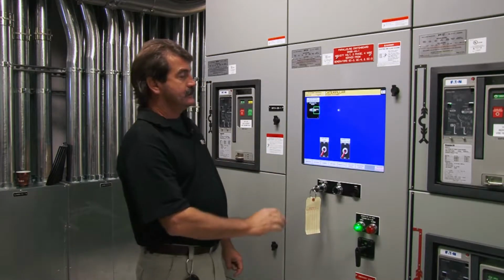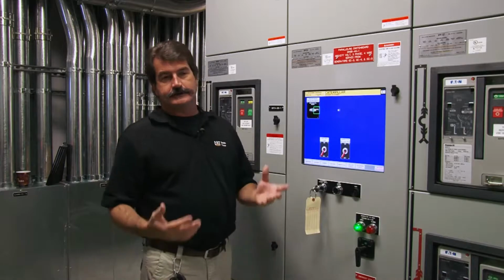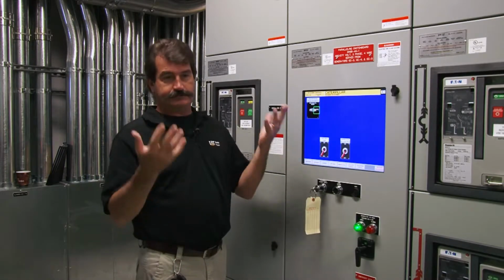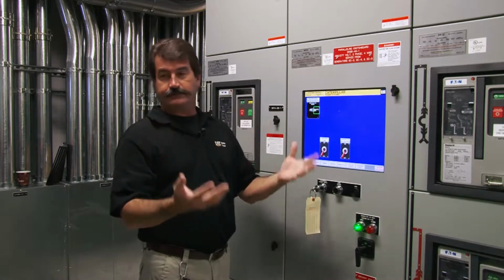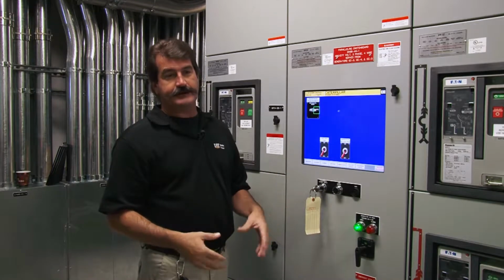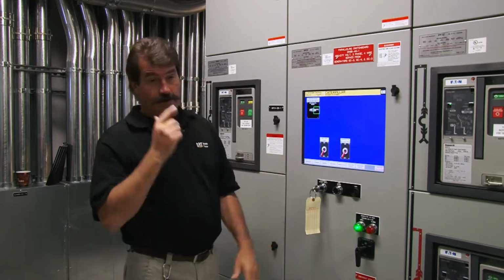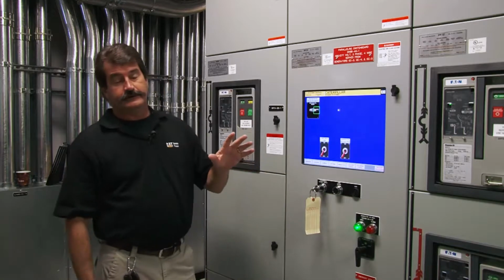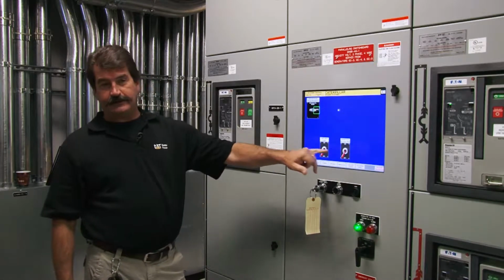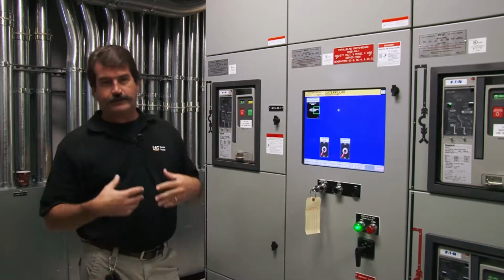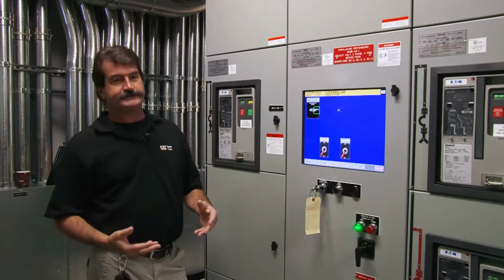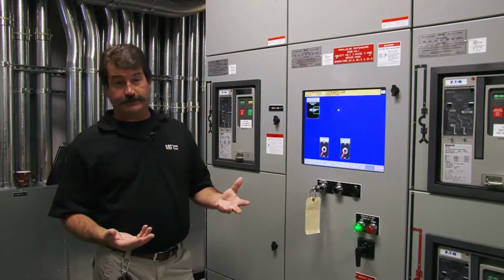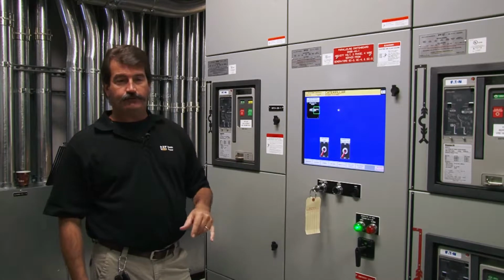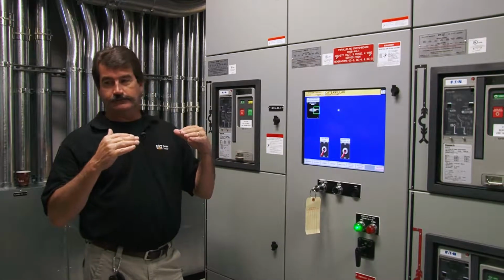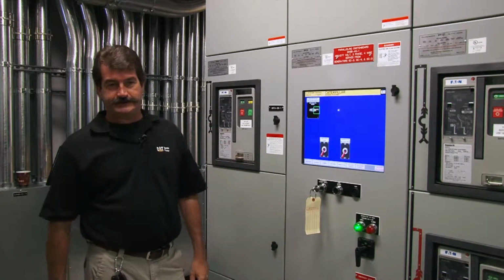Generator no-load test: the gens will fire up or start up and come to the bus, close the breakers, come to the bus, and sit there for as long as you have that switch in on. There is no exercise time or anything else, it's going to sit there until you turn them off again. And whenever you take them off, they're going to go into cool down for 5 minutes after that.